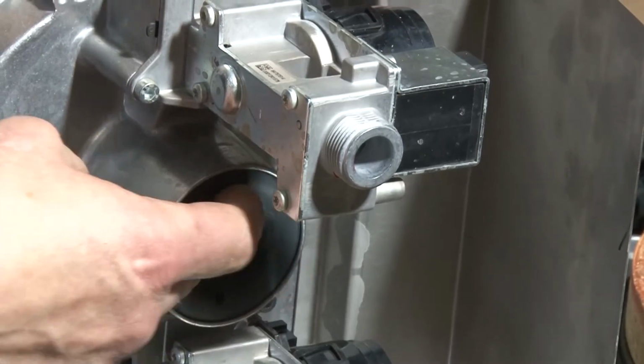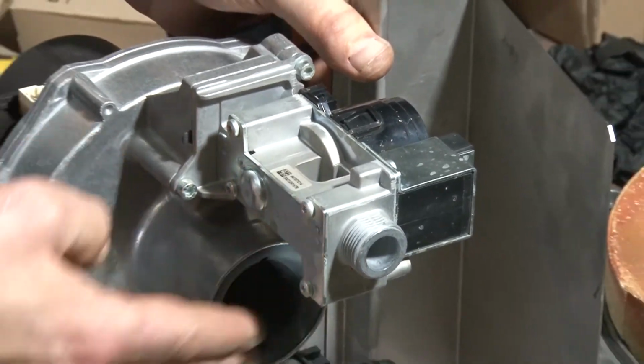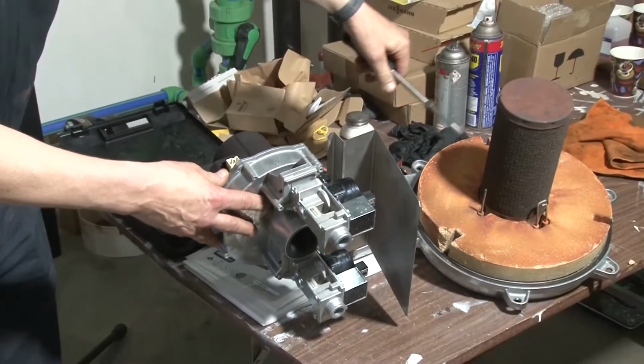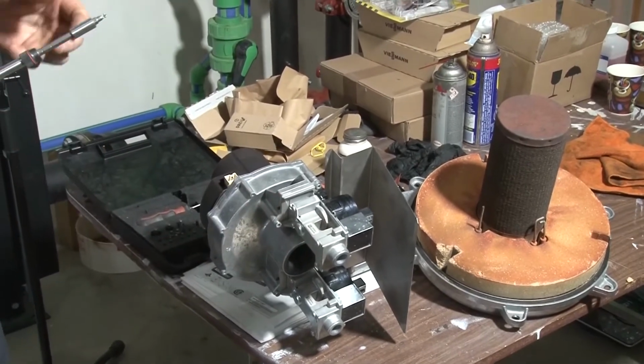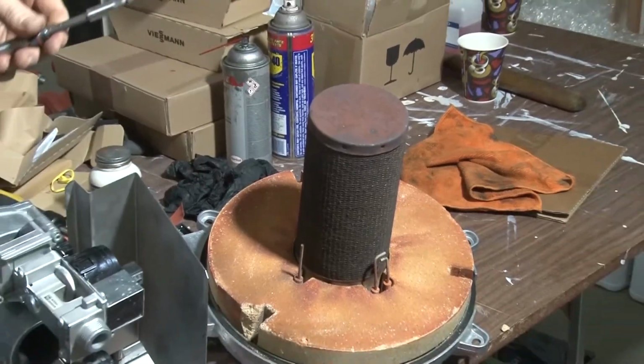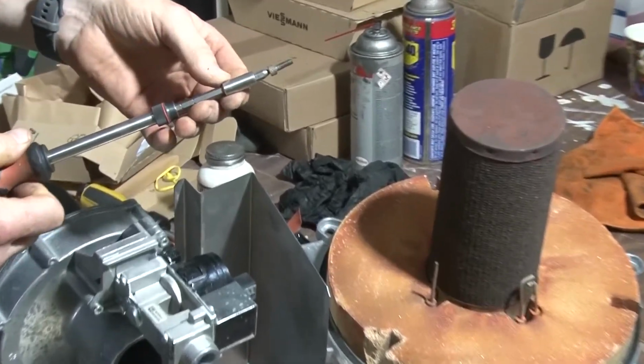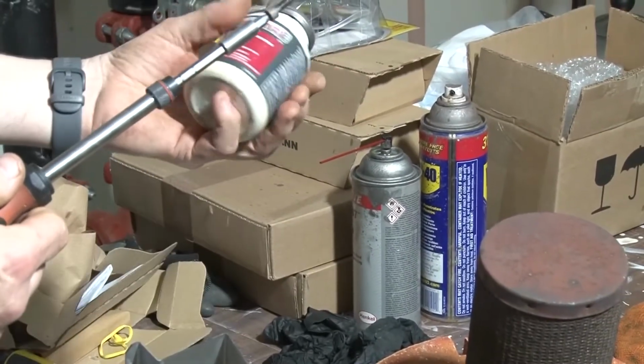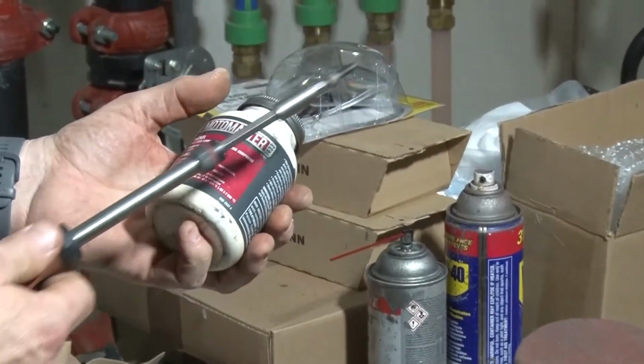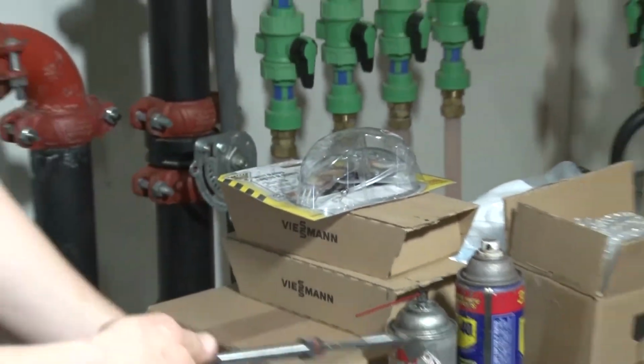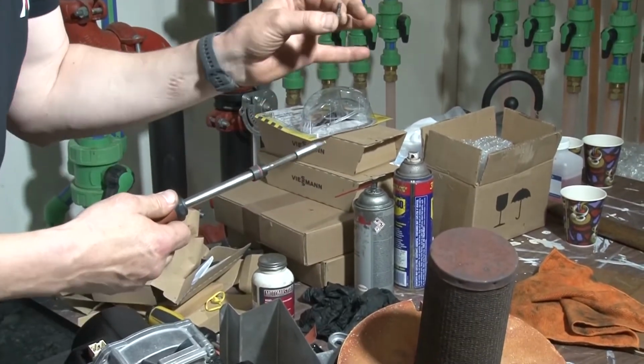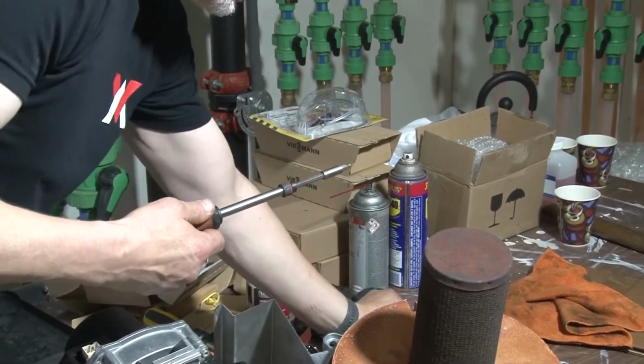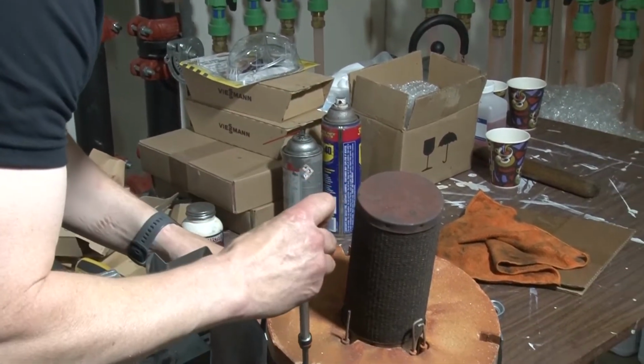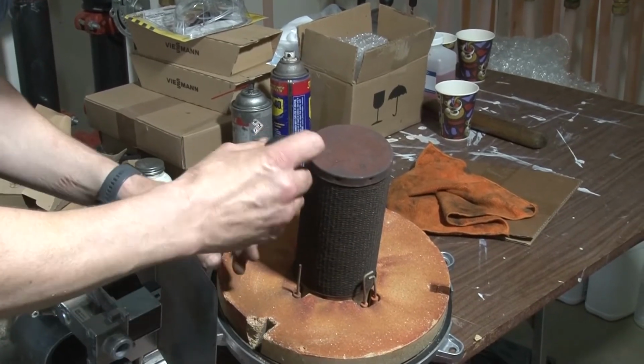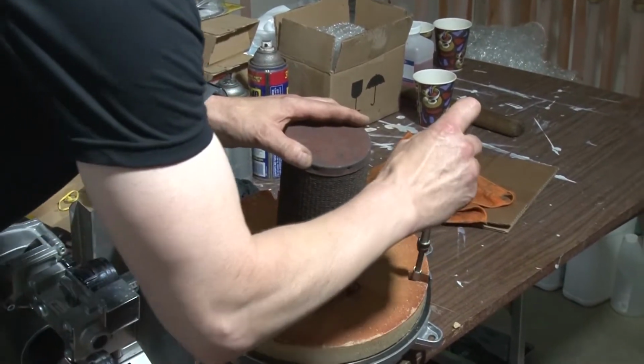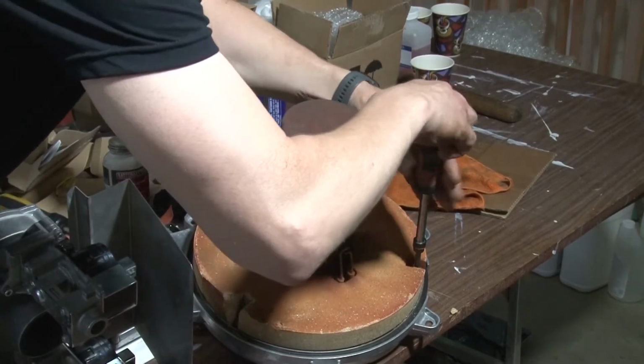But if you find a lot of dust and debris in here, that means that you've got dust and debris going up through your burner tube. So it needs to be addressed and we need to service it. And you can see this guy's already got some of that anti-seize on it. So basically, this type of anti-seize is what we would use in here. It just essentially lubricates that connection so that these don't seize into the aluminum, right? So just make sure you know where you're putting these as you're taking them out. We've got 3 to deal with here.